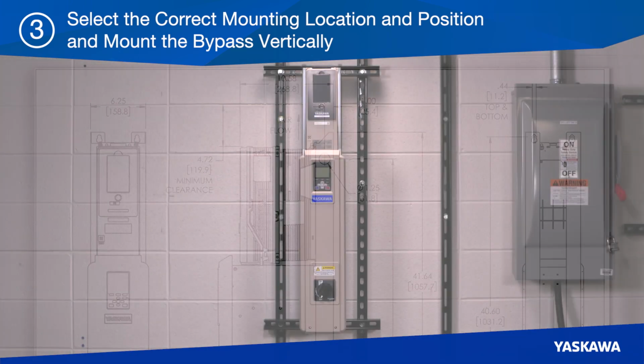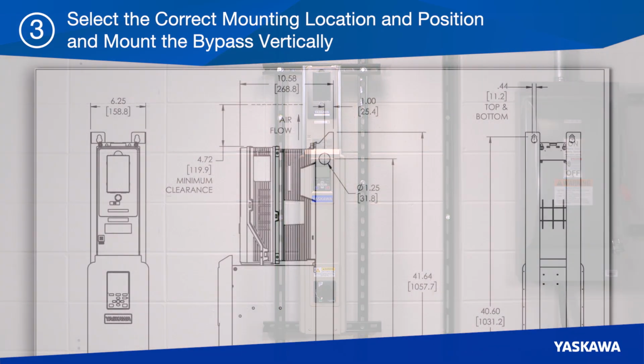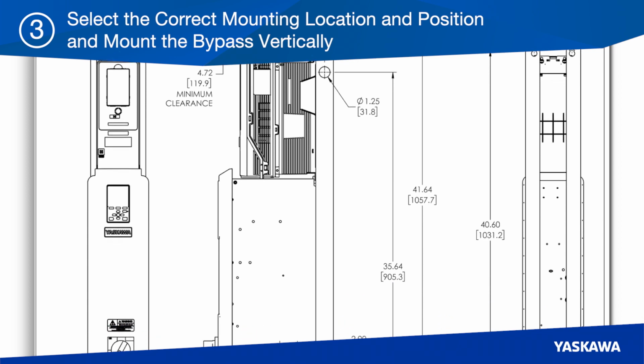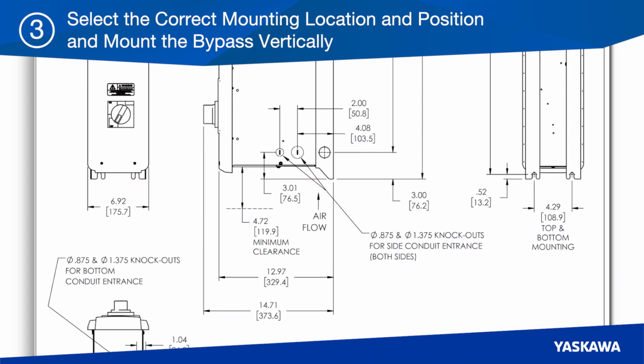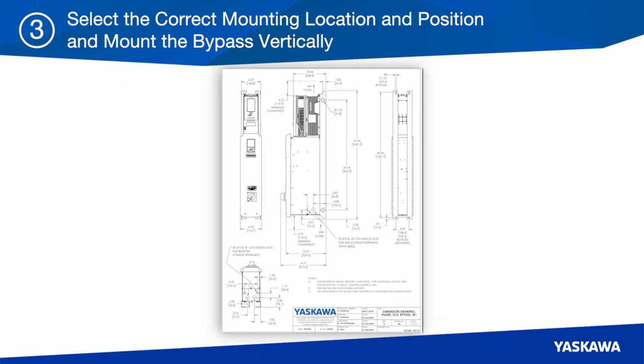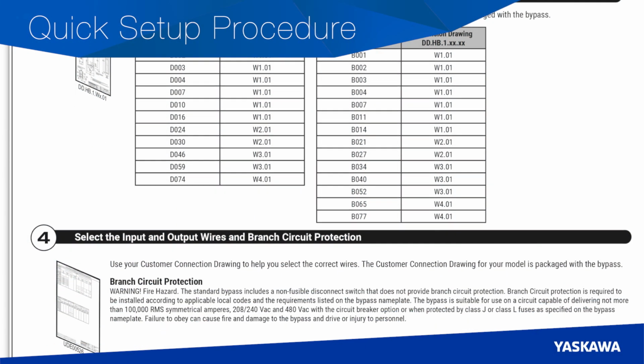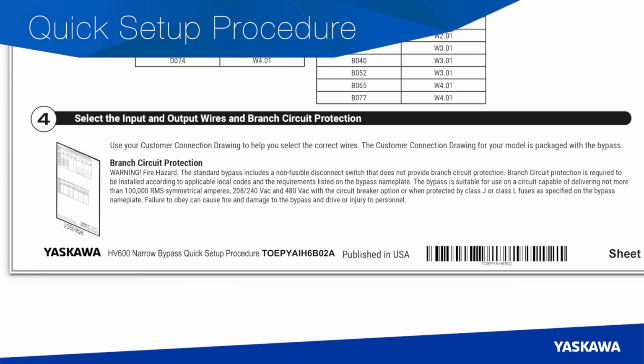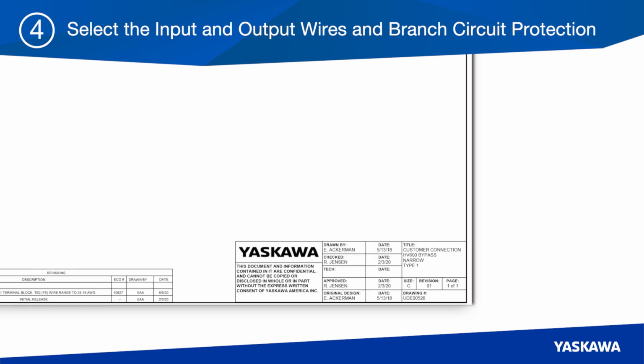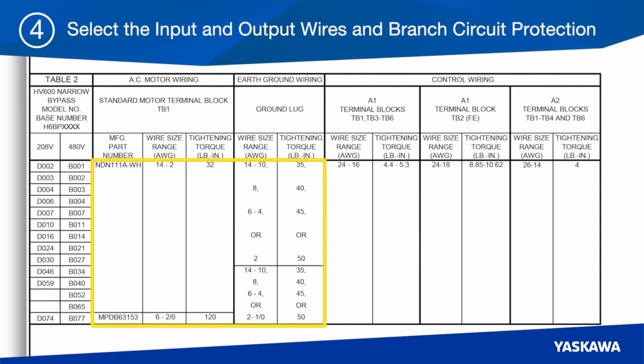In Step 3, use the enclosed dimensional drawings to mount the drive. Yaskawa provides dimensional drawings to assist installation planning and to ensure the proper mounting points. In Step 4, use the supplied customer connection drawing to select the proper motor and power wires and control wiring.